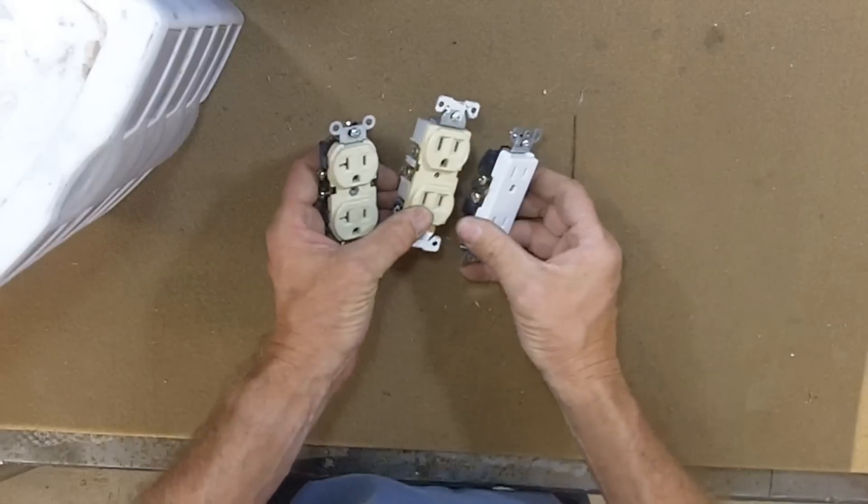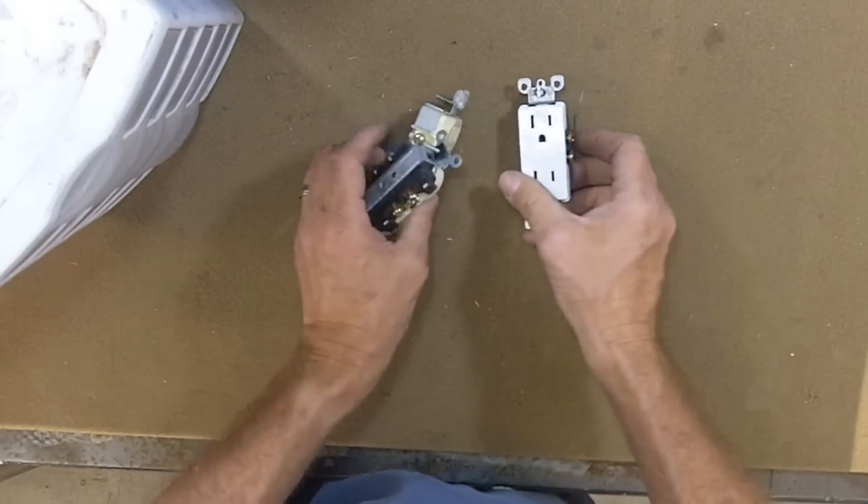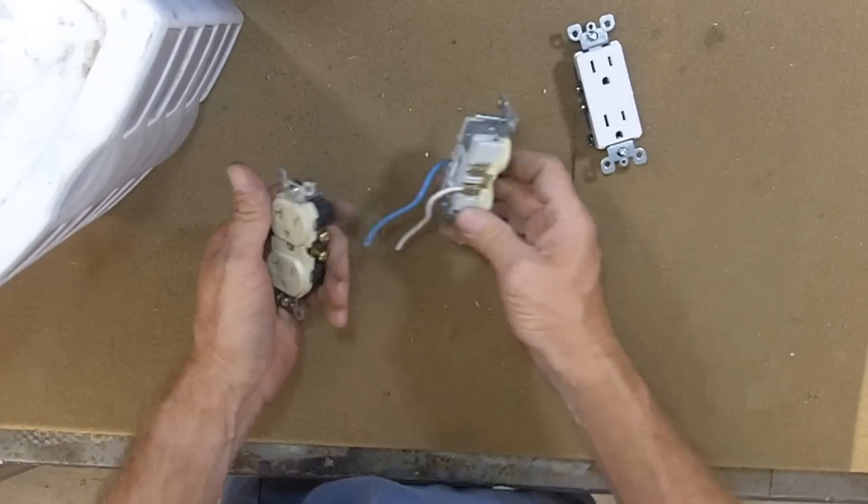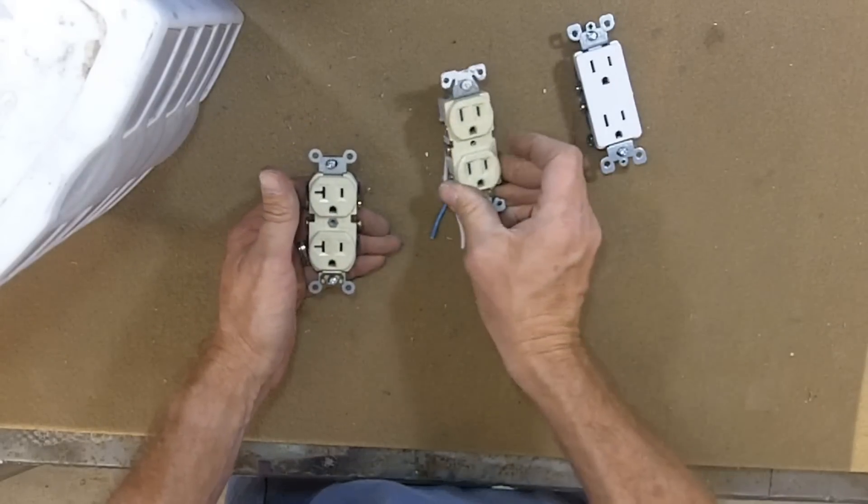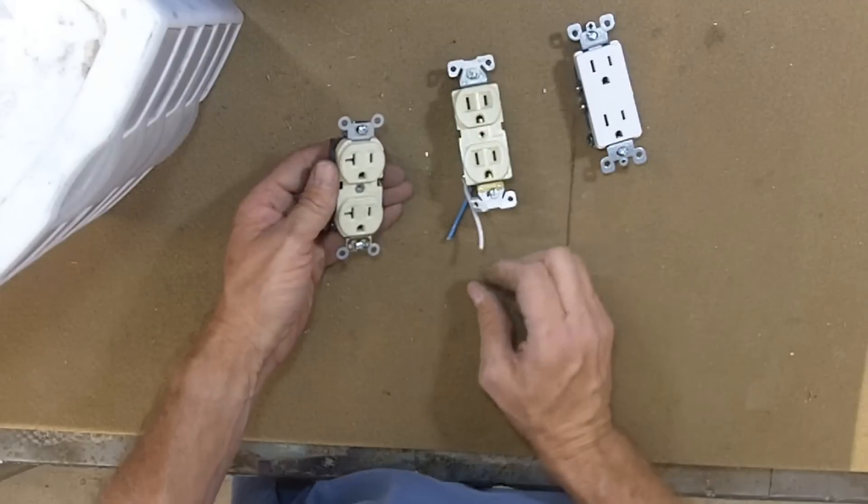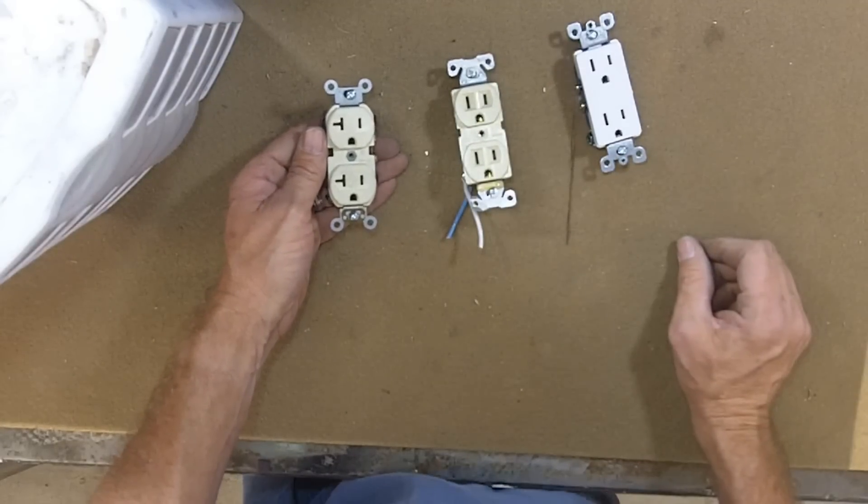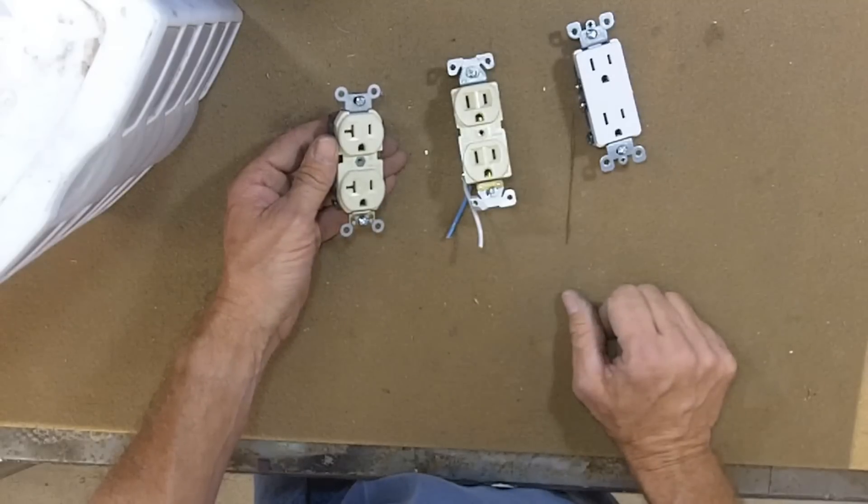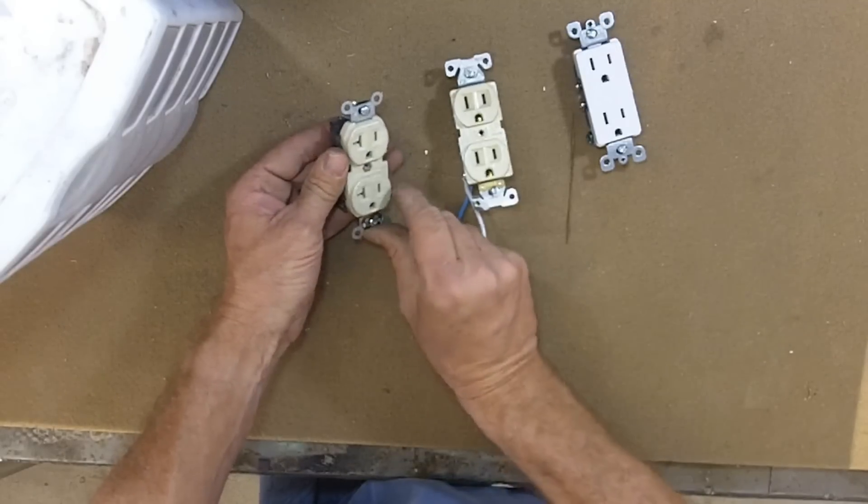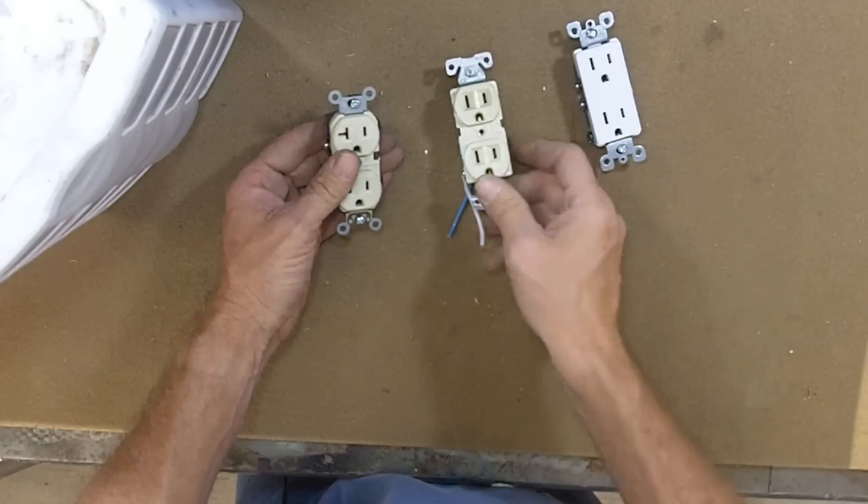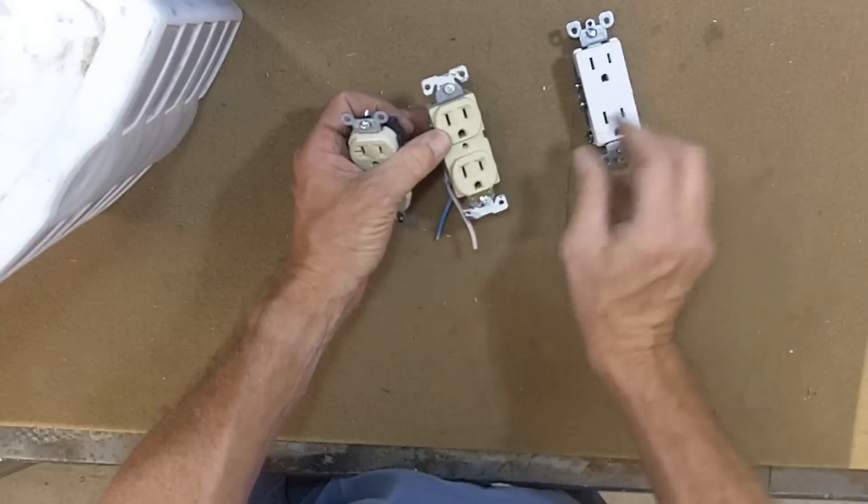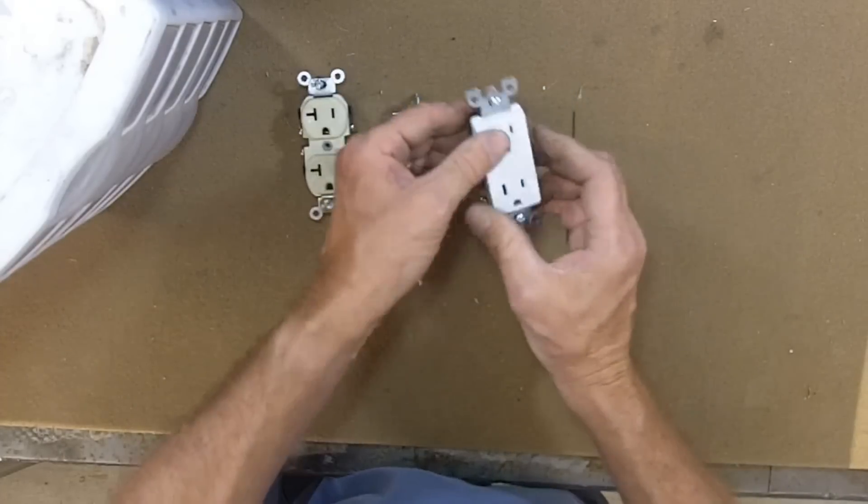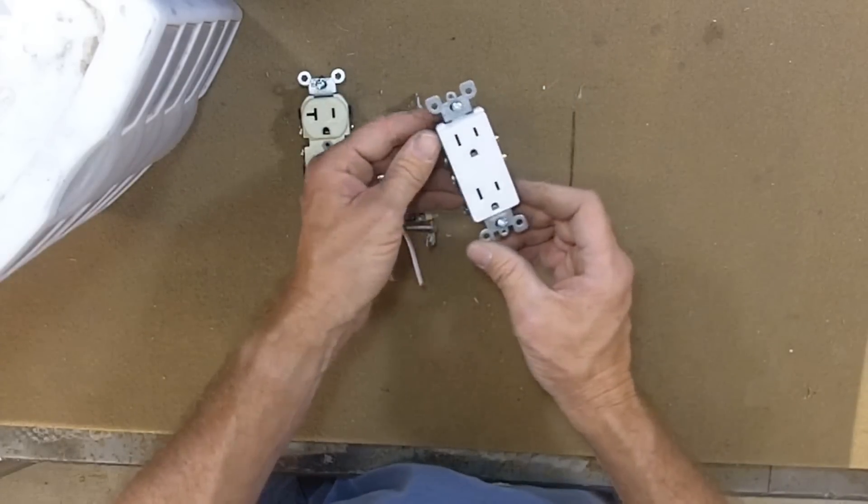What's the difference between these three outlets? Residential, this is more of a heavy commercial, it's only 15 amp, this is a 20 amp. I know it's a 20 amp, it's got the little side bar in there on the neutral side, also tells me right there, 20 amp, 125 volt, 15 amp, 125 volt, and this is just custom residential.